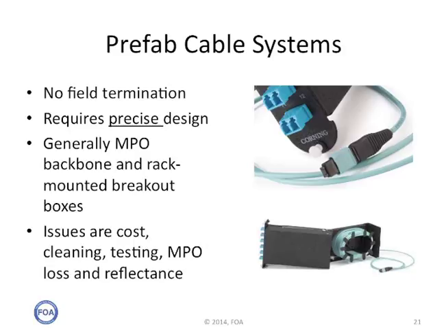MPO connectors have higher loss than LCs or SCs, so you have to watch your power budgets. These connections are very sensitive to dirt, must be carefully cleaned, and special microscopes are needed to inspect them. Whenever one is installing pre-terminated cables, one must have the protective covers over the connectors all the time during installation to prevent damage. Damaged cables will probably need to be removed and replaced, and a new cable may take weeks to get delivered.